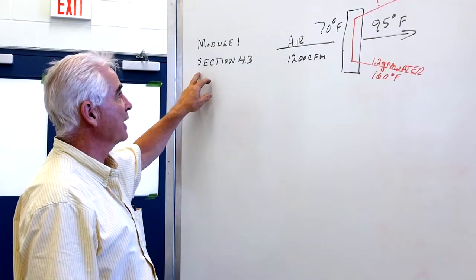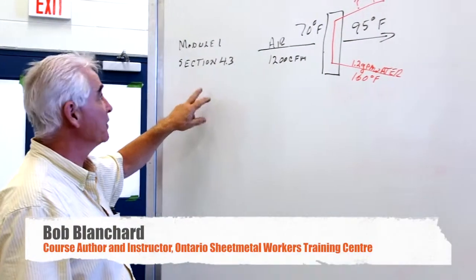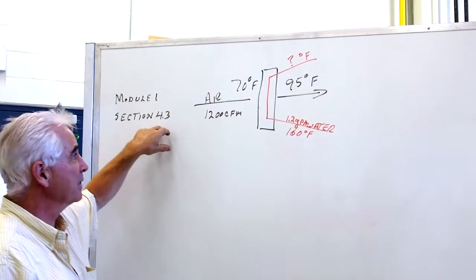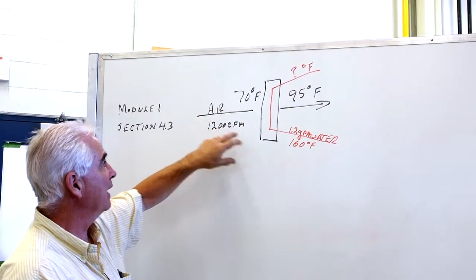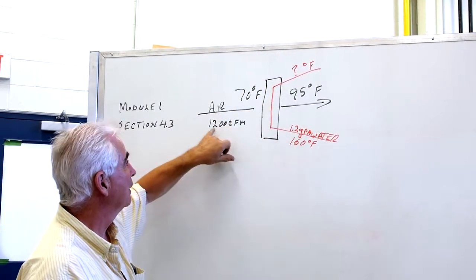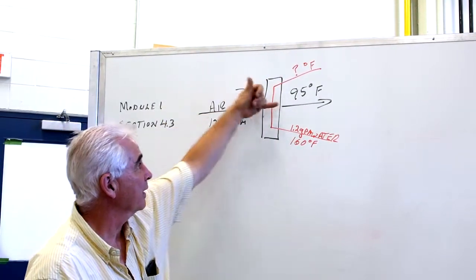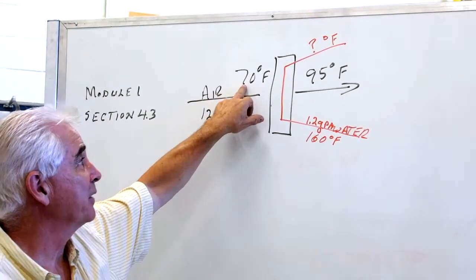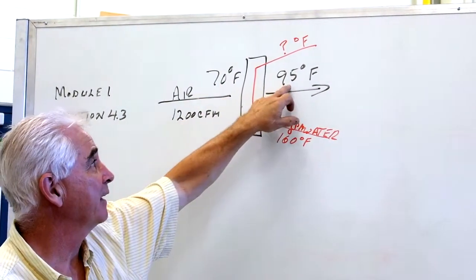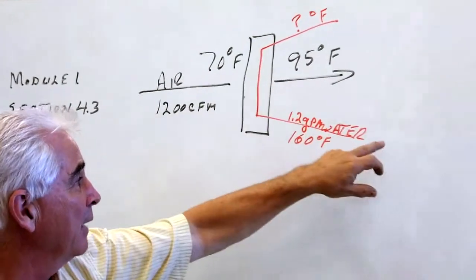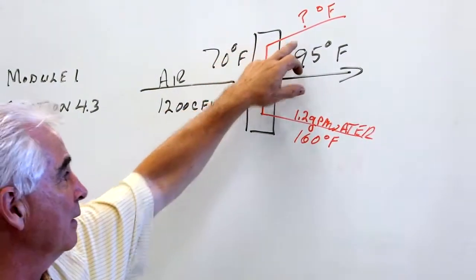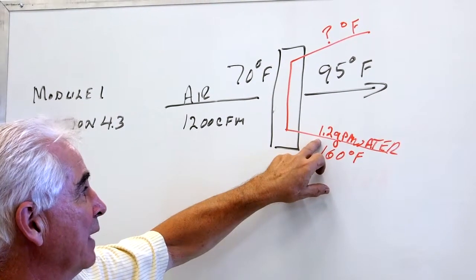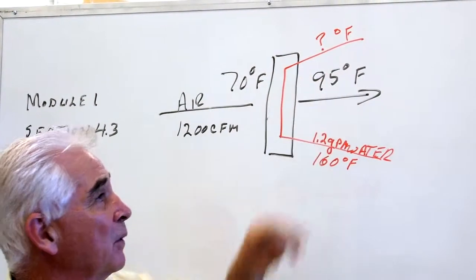This is an example of the heat balance equation from Module 1, Section 4.3. The question says: if we have a coil with air flowing across the coil at 1200 CFM, entering at 70 degrees Fahrenheit, leaving at 95 degrees Fahrenheit, and we have water flowing through the coil entering at 160 degrees at 1.2 gallons per minute, what is the temperature of the water coming out?